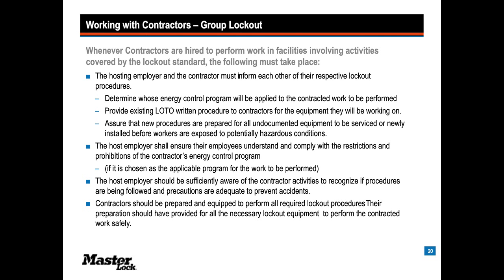A host company also should provide existing lockout procedures to contractors for the equipment they will be working on. Those procedures are the responsibility of the host to provide, and if they are not completed at the time that work is going to begin, a handwritten agreement, in terms of writing a lockout procedure on the spot, can be accomplished with both the contractor and the host company walking down the machine and noting what's being done to lock it out.